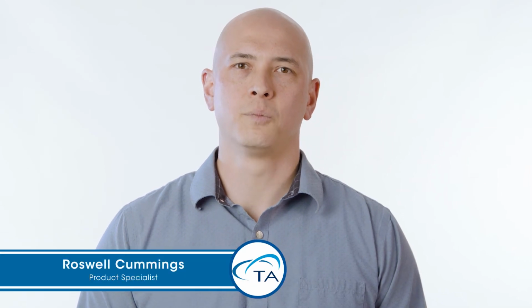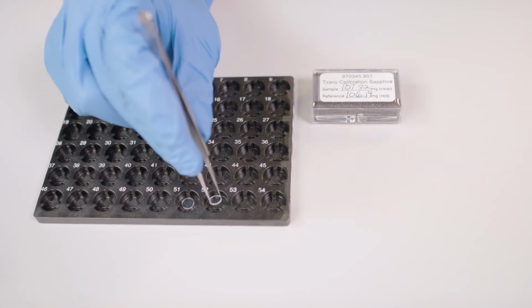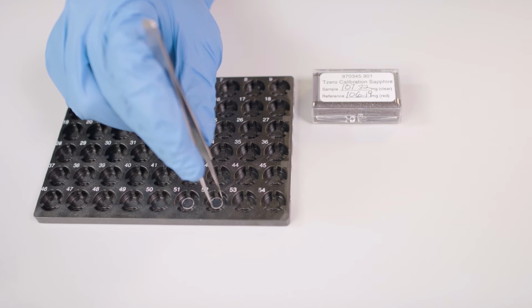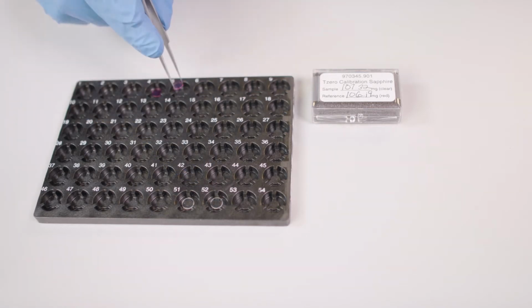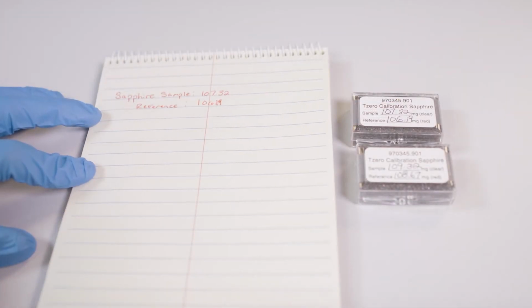In this tech tip, we'll show you how to set up a Tzero calibration on your X3 DSC. Before creating the Tzero calibration experiments in Trios, place the Sapphire calibration standards included in the instrument accessory kit into separate autosampler tray locations. Make note of the Sapphire masses and their corresponding locations.